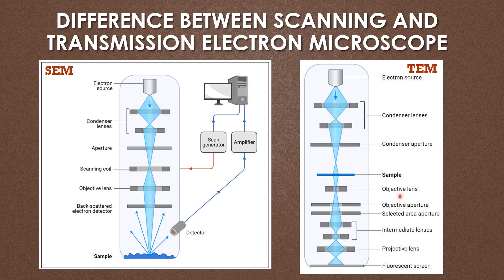In the SEM the objective lens is present above the sample, but in the TEM the objective lens is present below the sample. The electron source in the TEM produces an electron beam. In the SEM, two types of beams are produced: the primary electron beam, and after striking the sample, a secondary electron beam. In the TEM, a single electron beam is produced. Also, the TEM has a fluorescent screen, but the SEM does not. The SEM contains detectors and amplifiers, while the TEM does not.